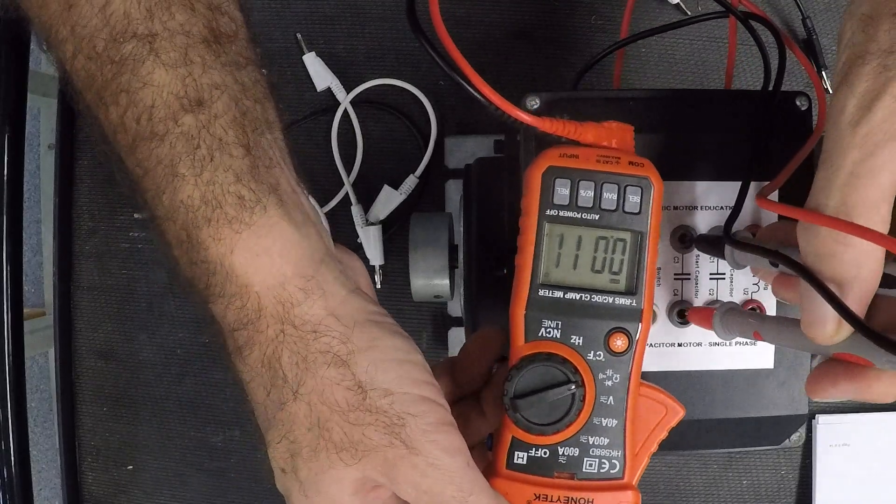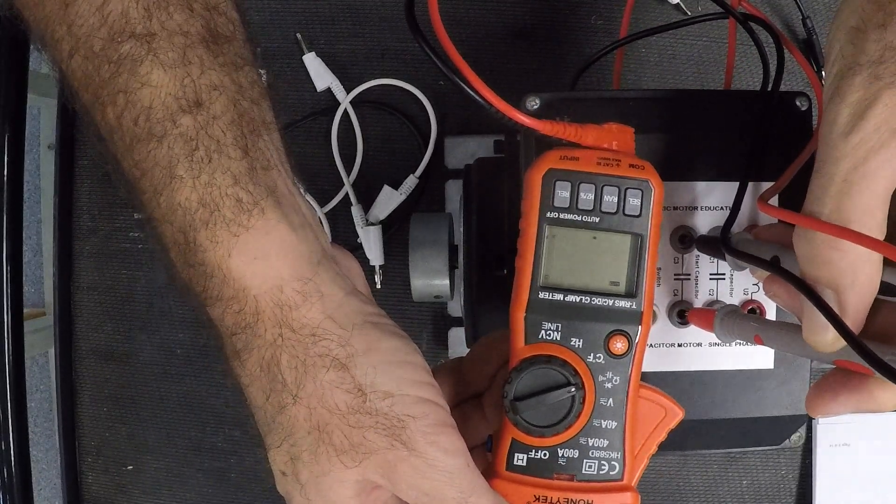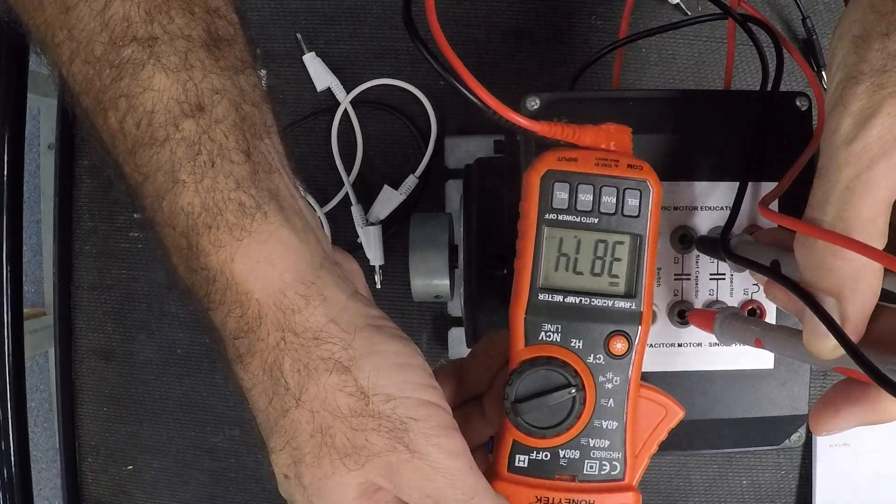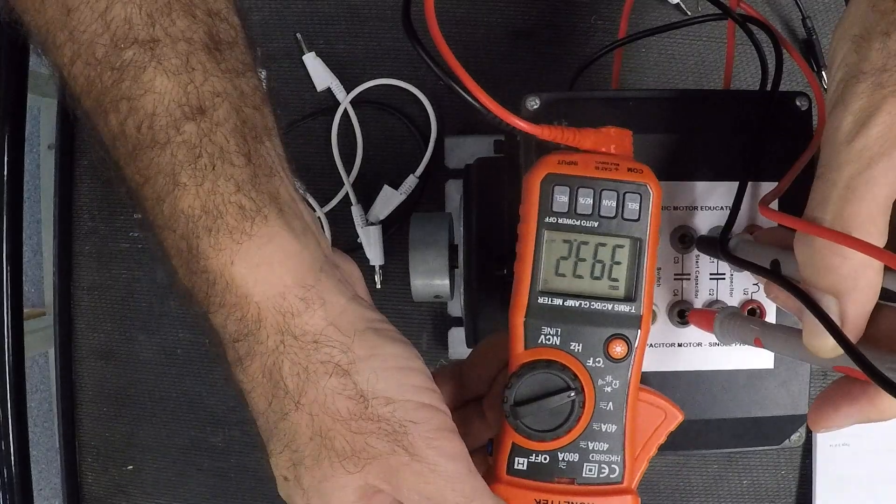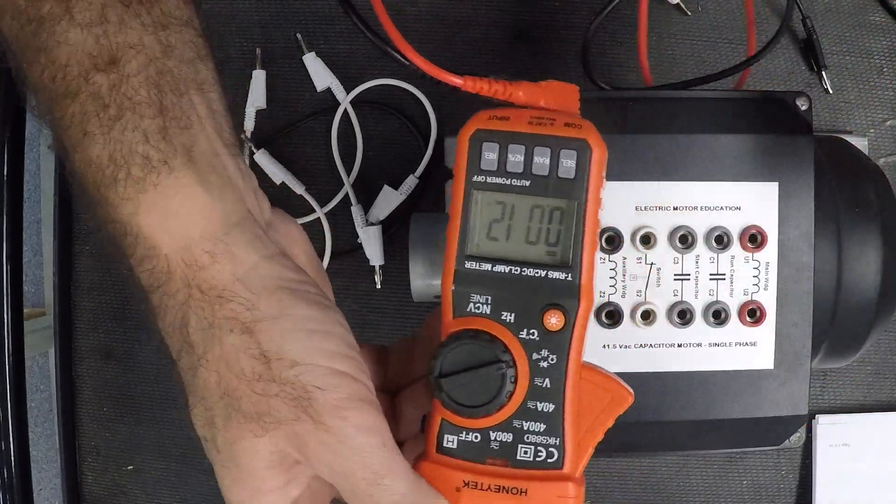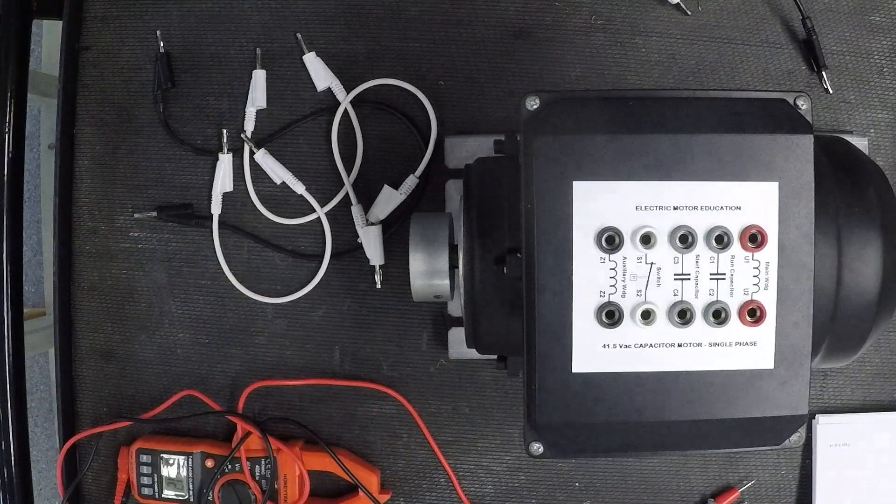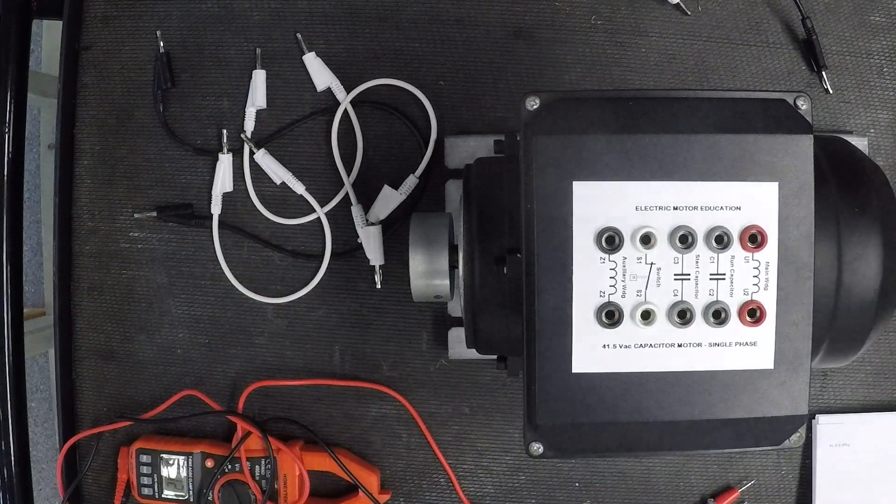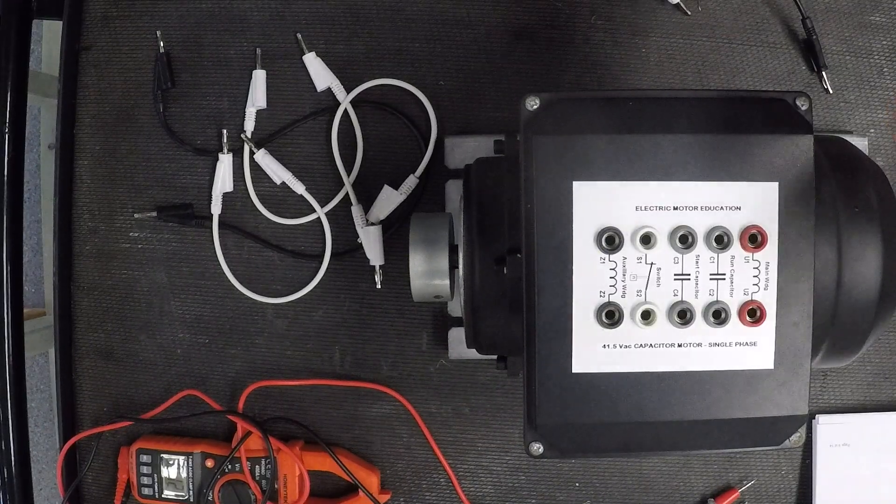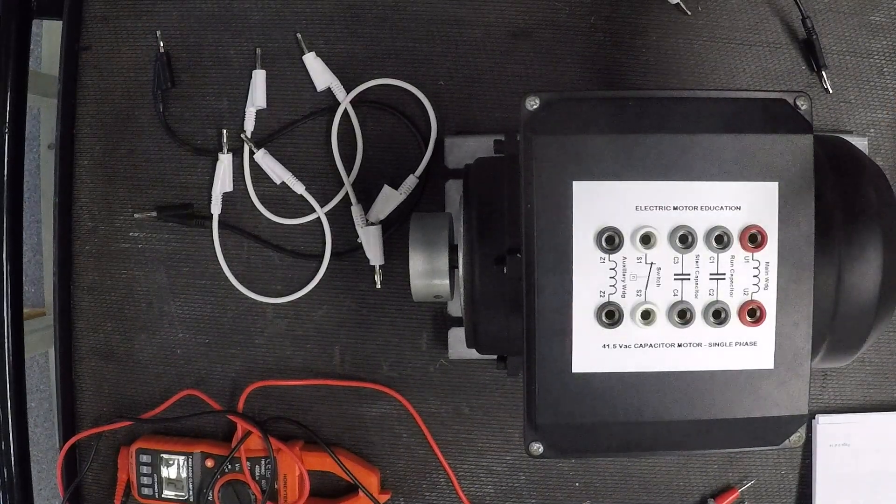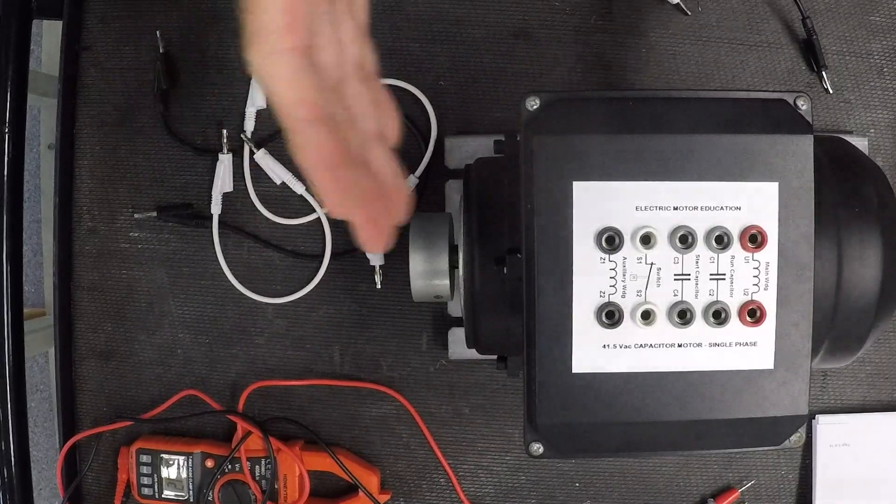If I go to my start capacitor, I should have a much higher reading on that one. Let's see if that's right. I get 384 microfarad. To me, this is just indicating that the capacitors are in working condition. I will have to do a physical or visual check to see if they're bulging or leaking, because we need to make sure the capacitors are good. At this stage, I'm happy with that.